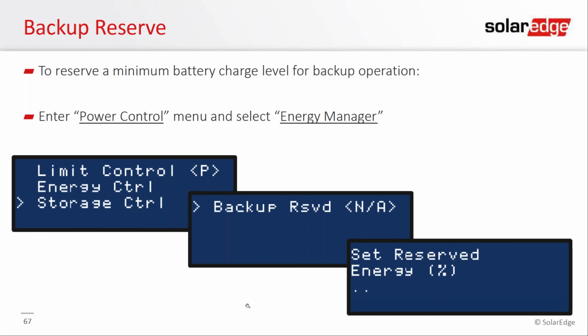So if you don't turn off your loads, what will happen is the inverter will just wait until it has enough energy to supply power to those loads. And when it does, it starts supplying power, and then any excess energy charges the battery.